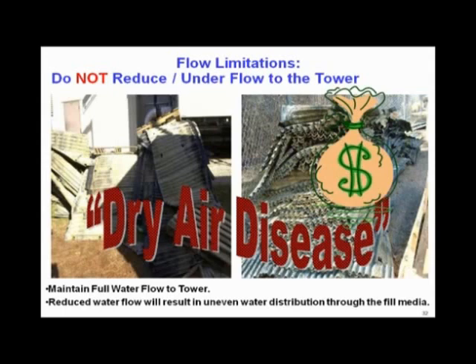In cold weather, with just that one small chiller, how many cooling towers did they run? They ran all three of them. With variable speed drives, they were just accumulating rocks all over their towers. There is a minimum allowable flow on those towers and you have to pay attention to it, or you'll face enormous bills like this. Then they blamed the chemical treatment contractor — but it wasn't their fault. The problem was simply insufficient minimum flow.